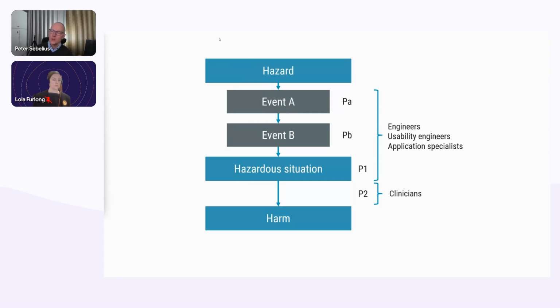When you do risk estimation or probabilities, the way you should do that for most medical devices would be to say, what's the probability of occurrence of harm in conjunction with one single use of the medical device? That is the best way. Now, some medical device manufacturers say, what's the probability of occurrence of harm for the installed base that we have? Which means that it basically changes the more you sell, the more likely it will be that you have a harm on your hands. So the best way of doing this would be per use, I think.